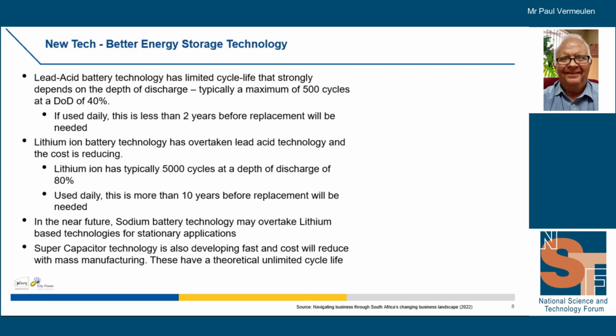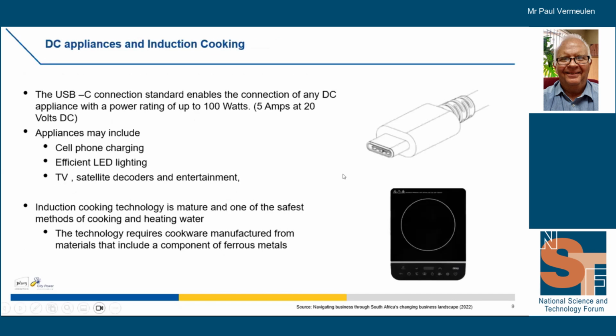And this is where lithium-ion battery technology has already overtaken lead acid in that regard. So lithium-ion typically has a 5,000 cycle at a depth of discharge of anything up to 80%. So it's a lot more usable from that perspective. And that would mean a 10-year useful life before you would need to replace it. We also see a lot of horizon stuff in terms of sodium technology may overtake lithium, be a lot cheaper, and be more suitable, of course, for stationary applications. The lithium technology is very light and compact and energy dense, so it's suitable for electric vehicles, for example, but there may be other technologies cheaper that are more suited for stationary applications. And also supercap technology is also developing fast, although it's very expensive at the moment. The cost should come down in the future.